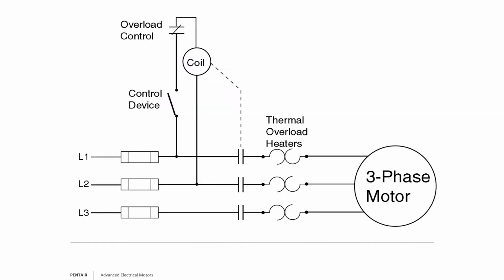When you connect these, you can connect the relay using the power coming in from the line. So you got your L1 line coming in before you hook it up to your start relay, of course. On the live side, you'll pull your current off. You have your control, be it a pressure switch or whatever. When the pressure switch closes, for whatever reason it might close, on demand, if you're using a pressure switch or timer, it'll pass the current. The current will go into the coil, pull down on the magnet, and energize the pump. Remember, thermal overloads or heaters, when you're talking three-phase, are typically add-ons. You have to add them on. They're not going to be built into the motor typically.